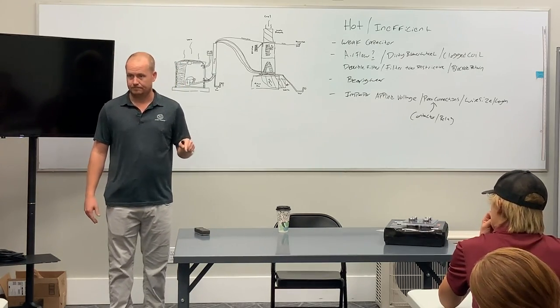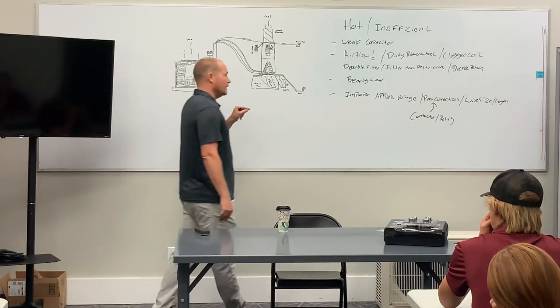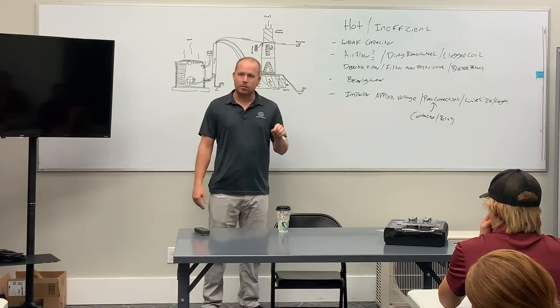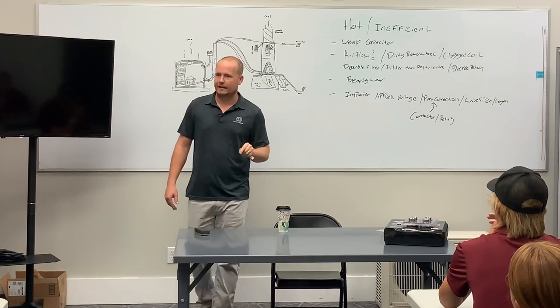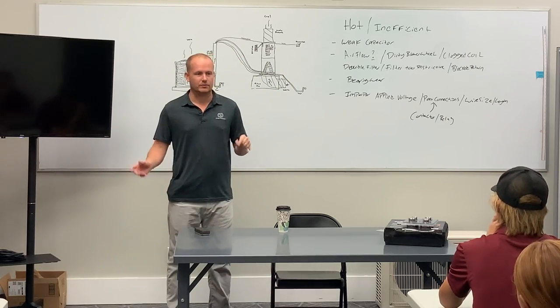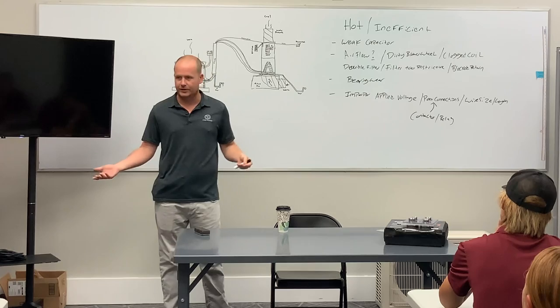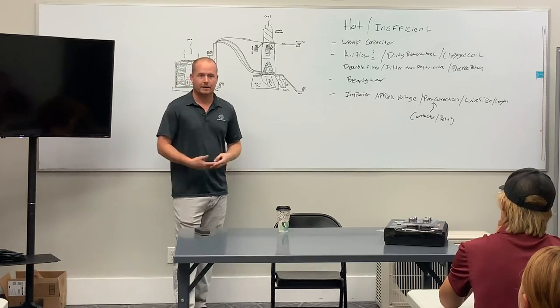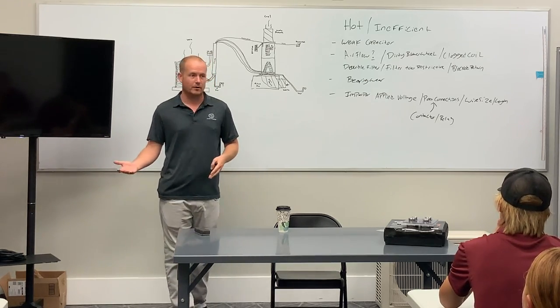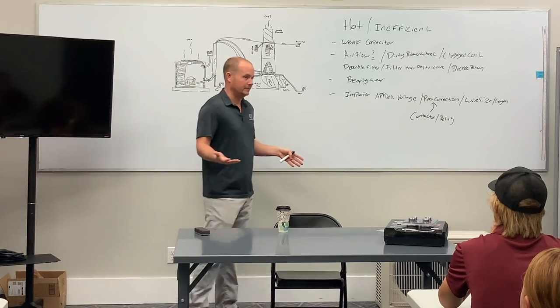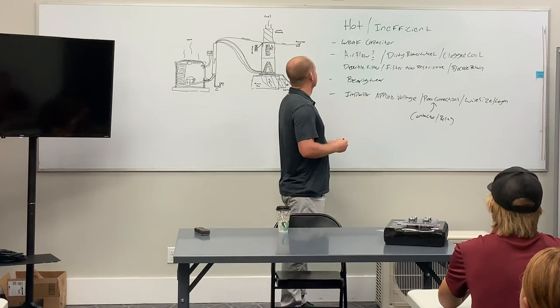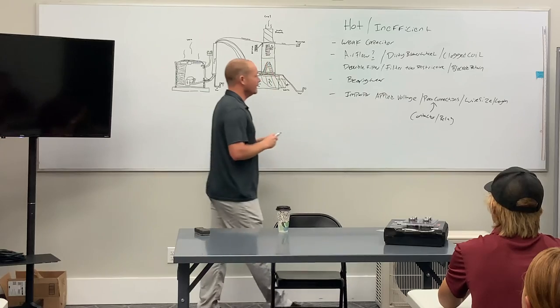Make sense? Mm-hmm. And in terms of what you really need to know, that's almost all you need to know, frankly. We can get really into the weeds of how capacitors work and what they do, and that's fun and it's good, but more than anything else, just know, when a capacitor runs weak, or you put one in that's too small, it results in a hot, inefficient motor. Right? Cool. So, I wanted to talk about that.